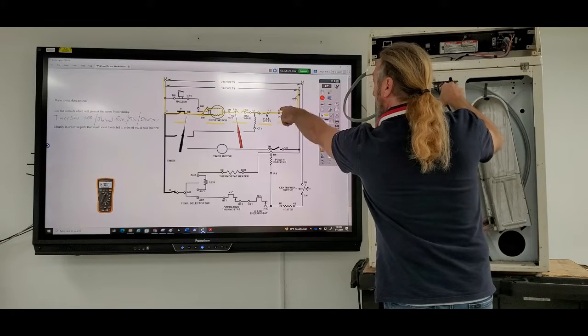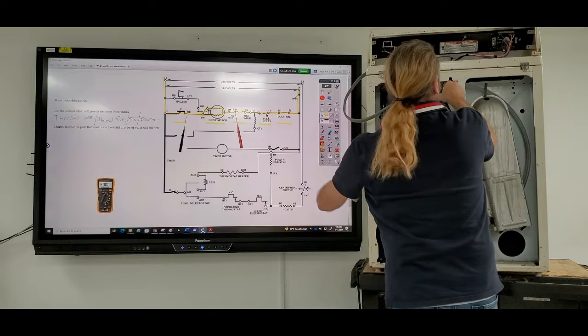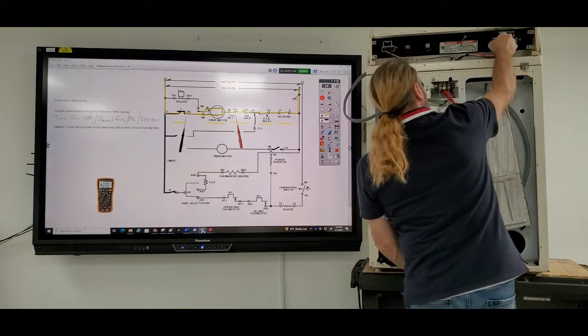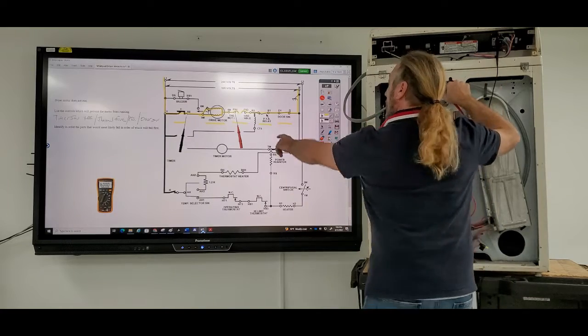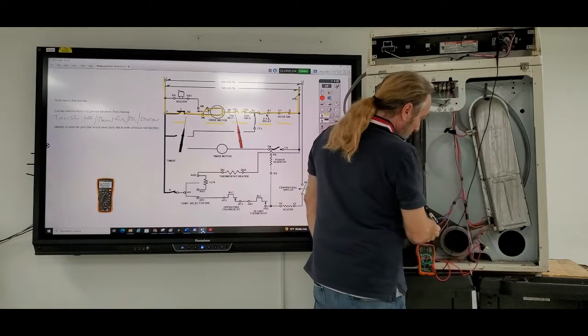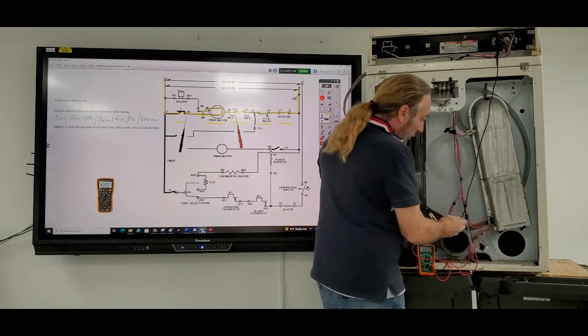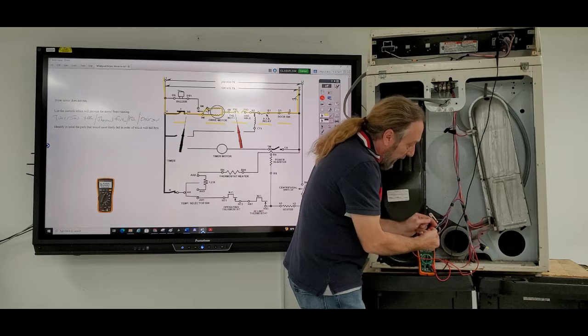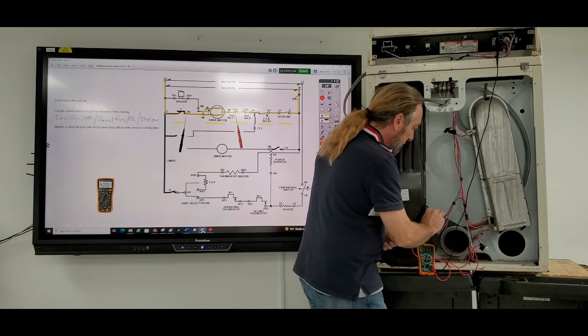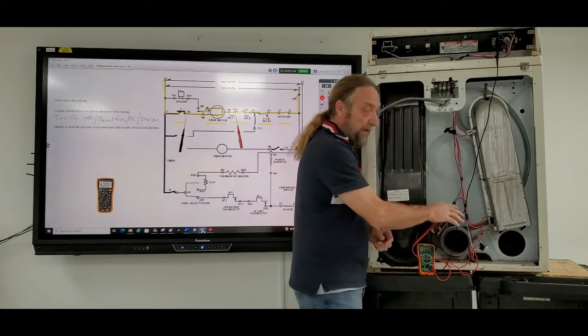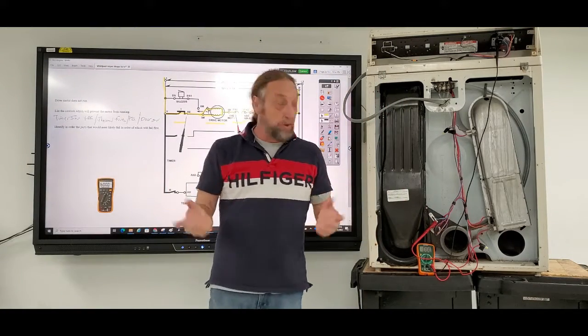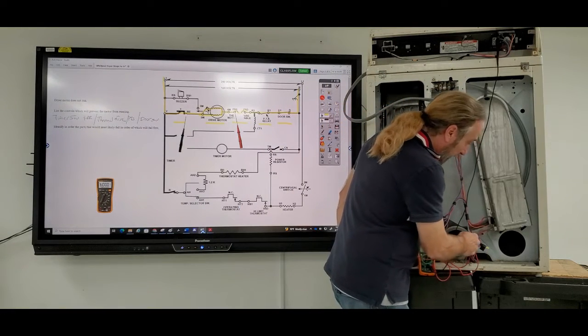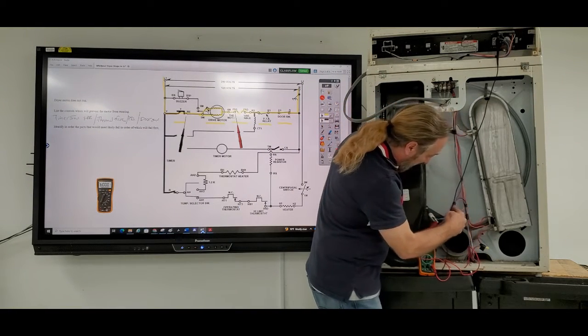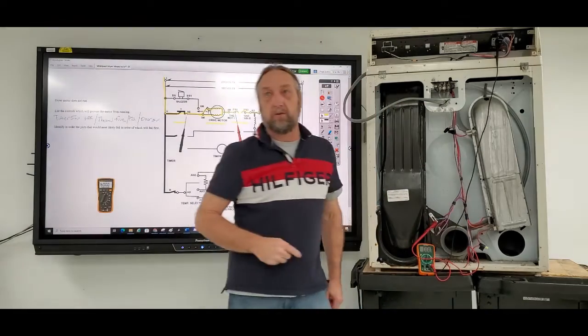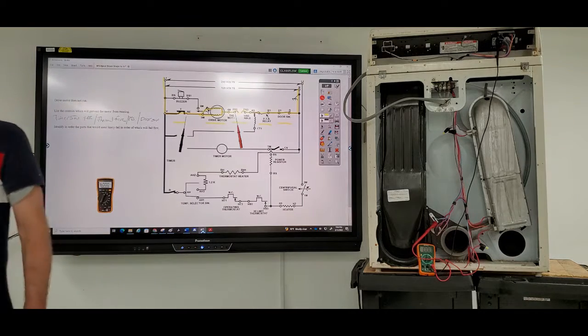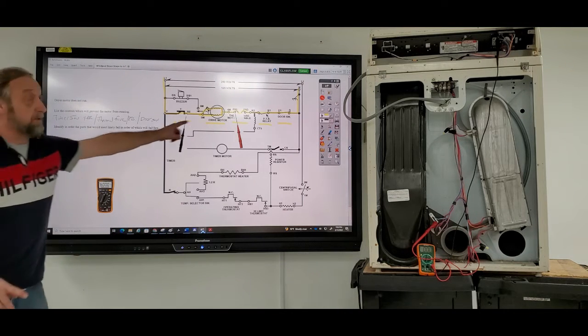So I'll take the black lead and put it on the timer terminal that goes to the motor, and the other lead on whichever terminal is FS1. On Whirlpool units they often mark the wires with letters, but I don't see it on this one, so I'll just pick one side of that fuse for now. If you don't know which wire it is, you can trace it — this blue wire goes to the one I'm connected to, which goes to the motor. That's as close to the motor as I can get at these points.